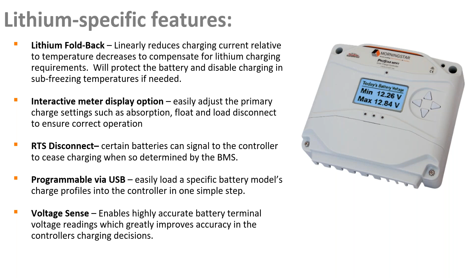And then voltage sense is something that has been unique for Morningstar products for a long time. I start to see competitors follow suit now because they realize that the accuracy of regulation can be drastically affected by voltage drop. And so you want to be measuring the battery voltage directly on the battery terminals. If your controller is positioned farther away or outside in a different enclosure, and there's some voltage drop in the wiring, you want to be able to compensate for that to maintain accurate regulation. So having the pair of voltage sense terminals on the controller allows you to do that easily, and builds in a little bit more intelligence for the controller to do its job.